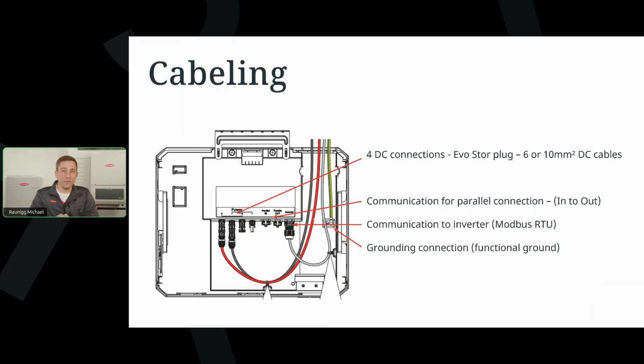And that means that you get 1 package for the 6 square millimeter cables and 1 package for the 10 square millimeter cables. And we also have written this down on the package, depending on the maximum amperage that you use. So mostly if you're installing Gen 24 Plus or Verto Plus, you will get a maximum amperage with Verto Plus, for example, of 50 amps, and with Gen 24 Plus of maximum 22 amps. So that means depending on the current that the system can draw, you need to either install 6 square millimeters or 10 square millimeters.